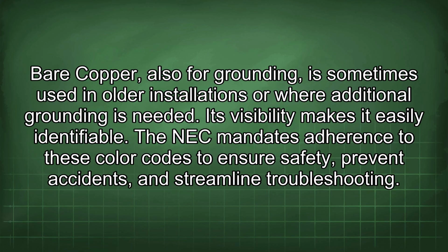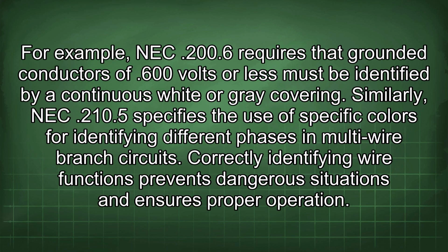Bare copper, also for grounding, is sometimes used in older installations or where additional grounding is needed. Its visibility makes it easily identifiable. The NEC mandates adherence to these color codes to ensure safety, prevent accidents, and streamline troubleshooting. For example, NEC 200.6 requires that grounded conductors of 600 volts or less must be identified by a continuous white or gray covering. Similarly, NEC 210.5 specifies the use of specific colors for identifying different phases in multi-wire branch circuits.